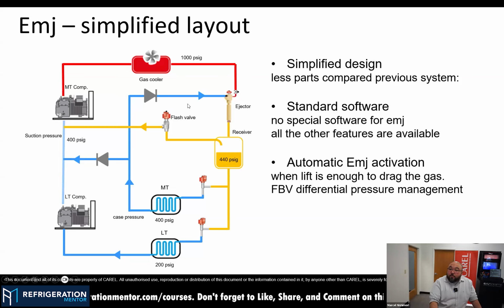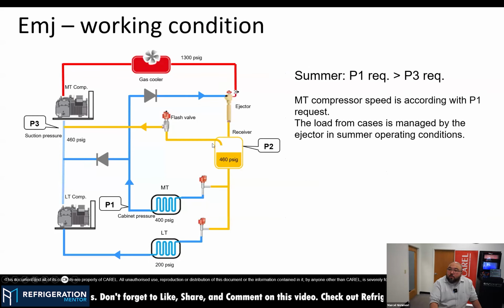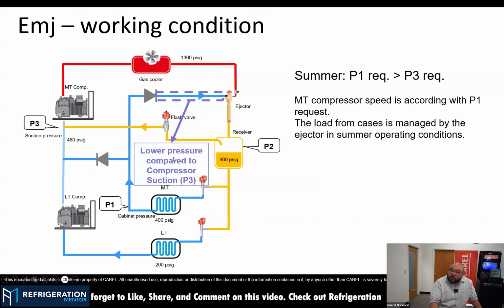During summer, this zone we will call the low pressure zone. Let me just go, then I will come back. During summer, we have this low pressure zone here, so we have a higher pressure on the ejector. I put 1300 PSI here, just as an example, and 460 on the liquid receiver. So I have a big delta.